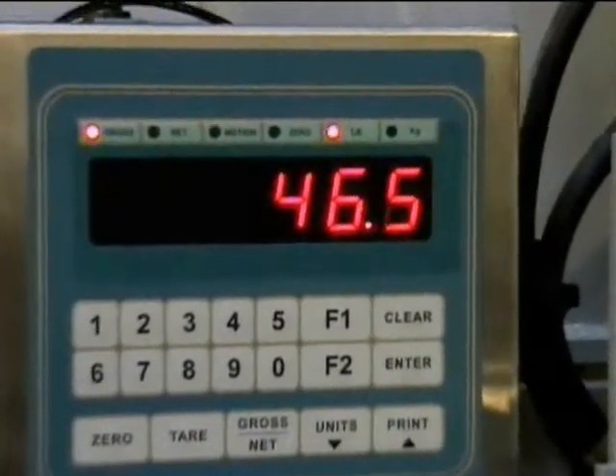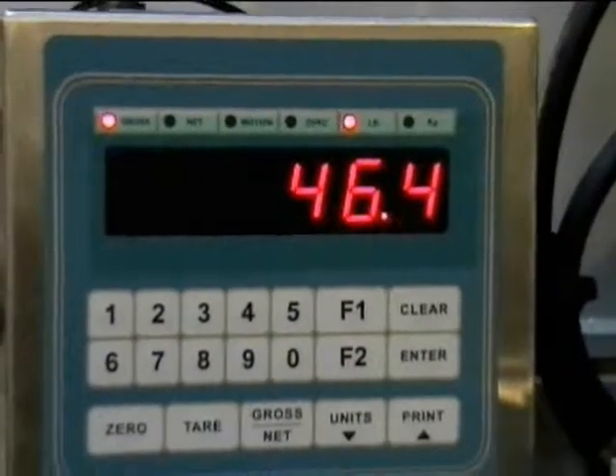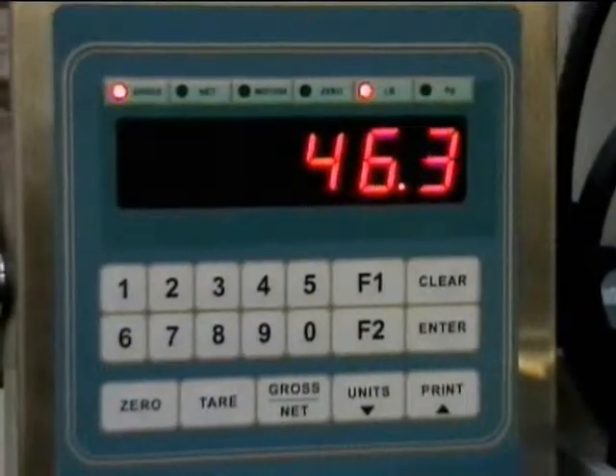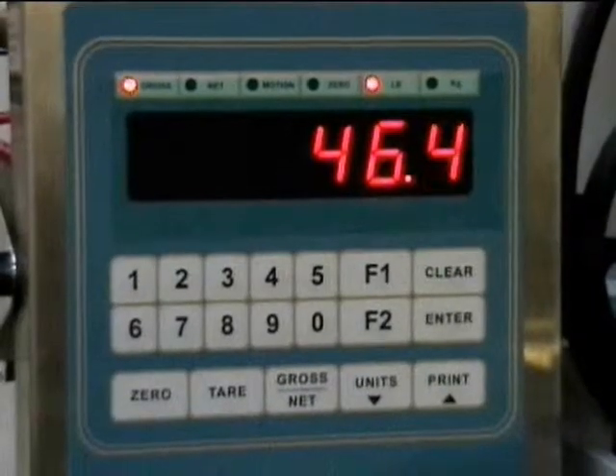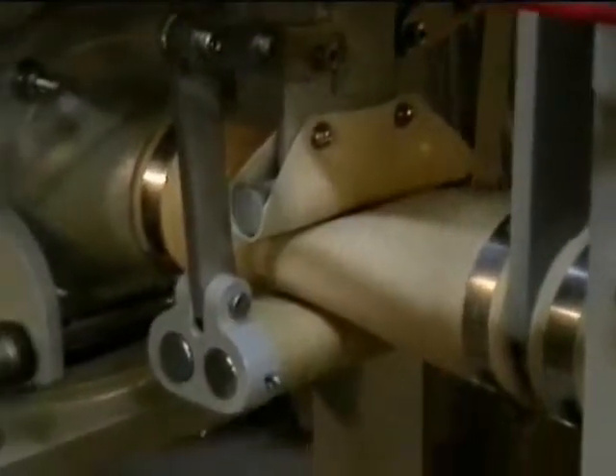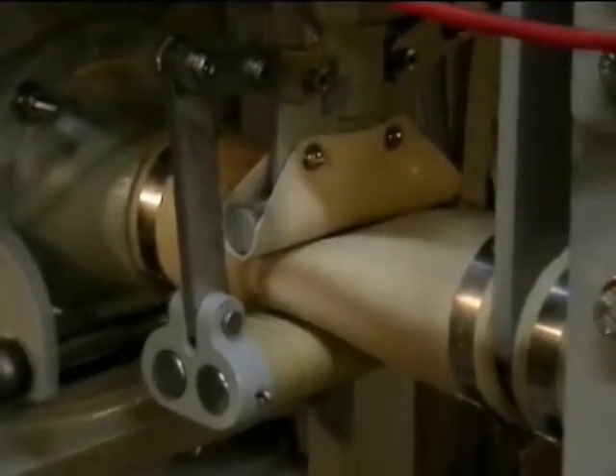By placing weight on the scale, we simulate a bag filling cycle, and as the weight on the scale reaches the value of set point one, the machine shifts to dribble mode, and the dual speed cutoff closes halfway, restricting the flow of product into the bag.